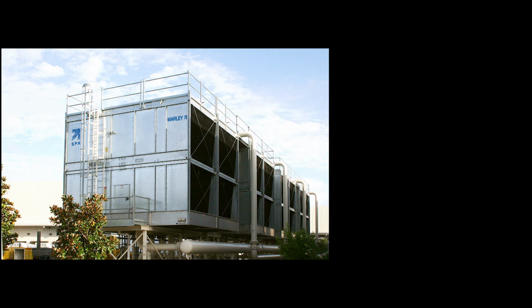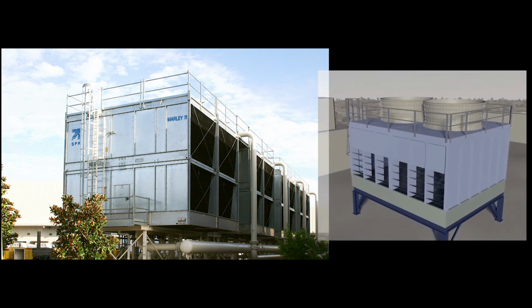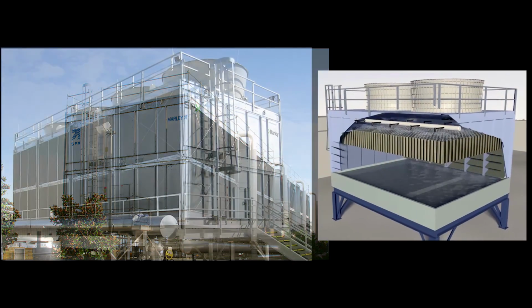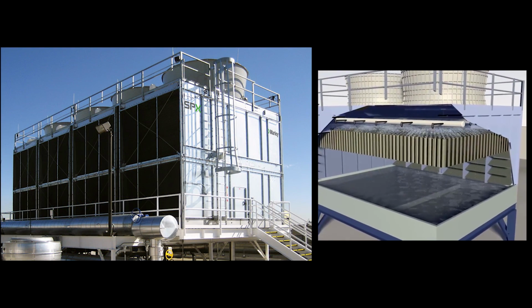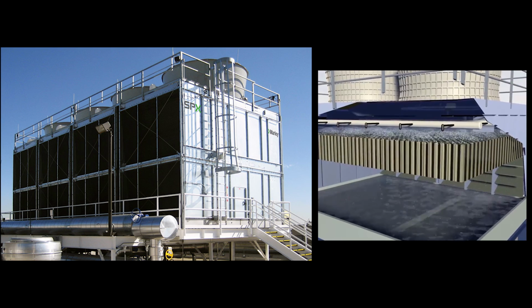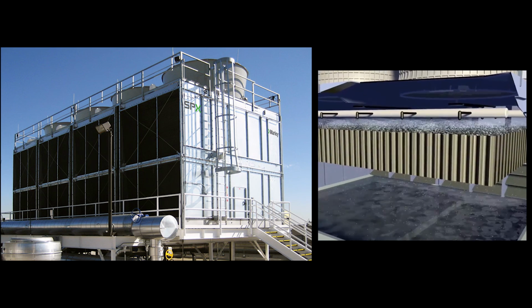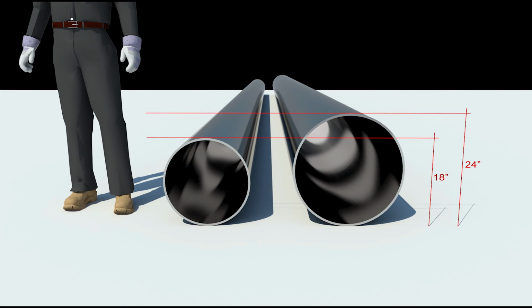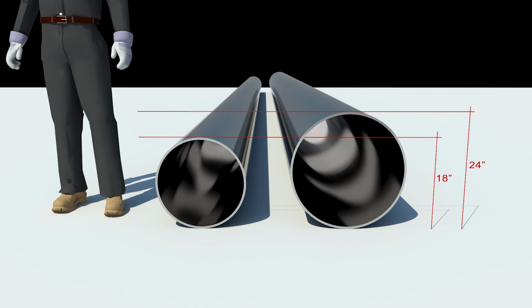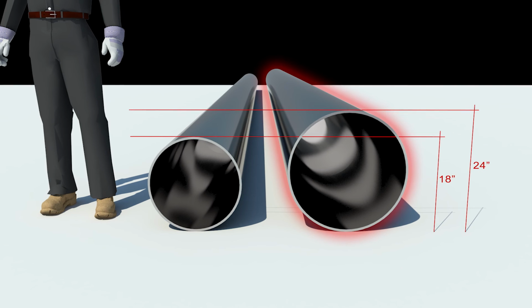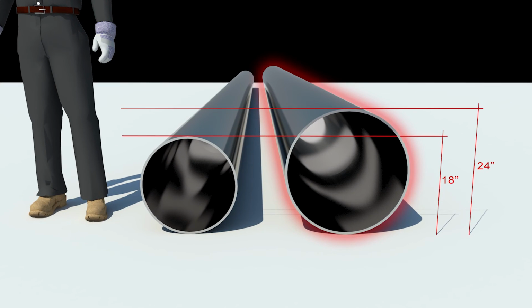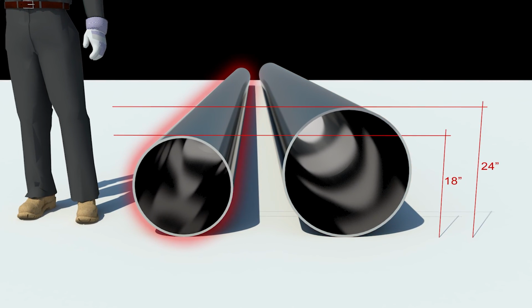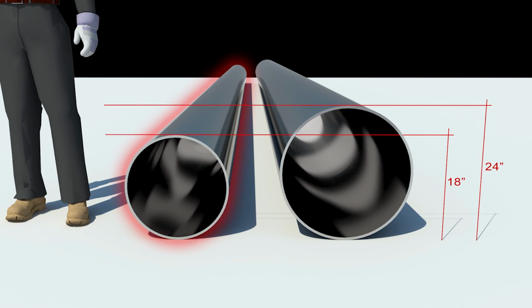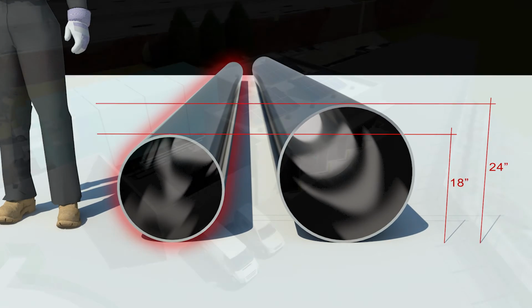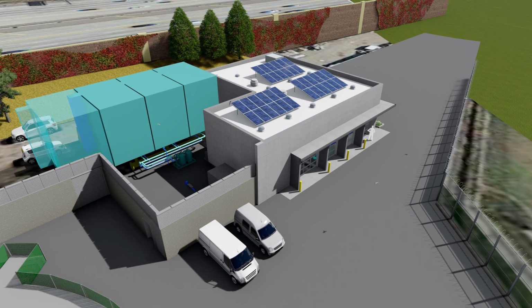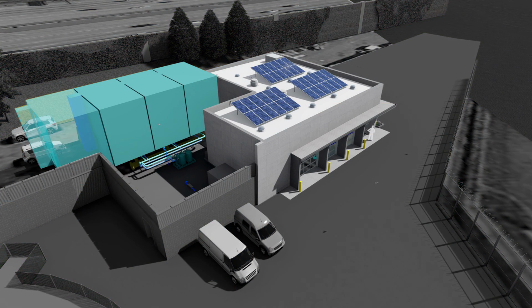The design also incorporates new efficient cooling towers sized to 76-degree wet bulb at 93-83 condenser water temperatures and equipped with high-efficiency mist eliminators and low-noise fans to minimize both drift and noise on the south side of the yard. Our proposed central plant design eliminates the need of routing 24-inch condenser water piping to the existing modular chiller plant, reduces the pipe size to 18-inch chilled water supply and return, and associated electrical feeders and conduits are reduced in size. It also consolidates all mechanical central plant equipment in one location.